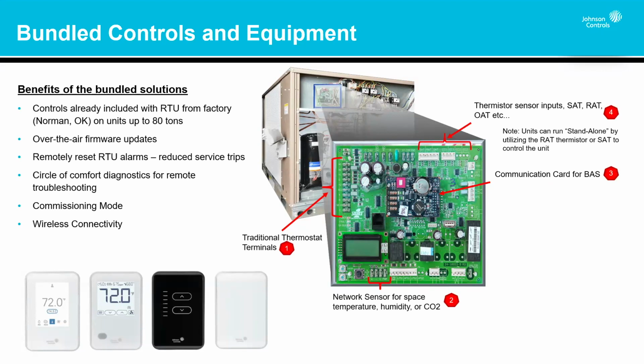One feature we've added is the ability to update firmware in rooftop units remotely, without physically going to the unit. Previously, before the latest release of Verasys, if we needed to reprogram or update firmware, we had to go to the unit with a USB stick. Now we can do it remotely, which is a huge time and labor savings. We also have the ability to reset alarms, reset timers, and override the unit for certain operating conditions, whether it's test and balance, commissioning, or simple use during construction.